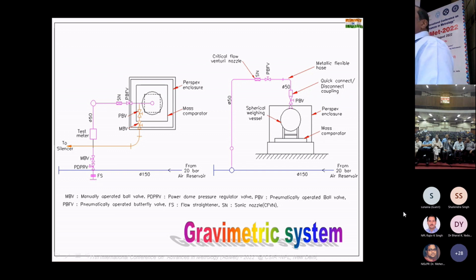But we have to see that when it crosses the critical condition, the flow rate reduces. So the overall testing is restricted till the downstream pressure reaches about 80% of the inlet pressure. Before that, we have to stop the flow. That is the duration of one particular flow rate. Nozzles are designed for a particular single flow rate, so to get a different flow rate, we have to use different nozzles, or by keeping a control valve here, we can regulate the pressure so that the mass flow rate will change. So this will keep the flow rate steady.